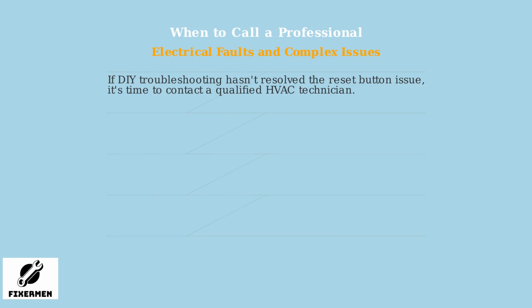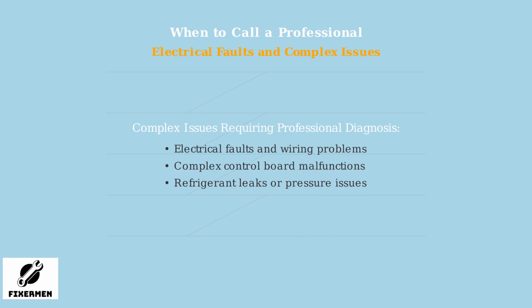If you've exhausted the basic troubleshooting steps and the reset button still isn't working, it's essential to call a qualified HVAC technician. Complex issues like electrical faults, control board malfunctions, or refrigerant problems require professional diagnosis and repair tools. Electrical faults involve wiring problems, voltage issues, or component failures that need specialized testing equipment. Complex board malfunctions may require firmware updates or component replacement. Refrigerant issues demand proper handling of pressurized systems to avoid health and environmental risks.